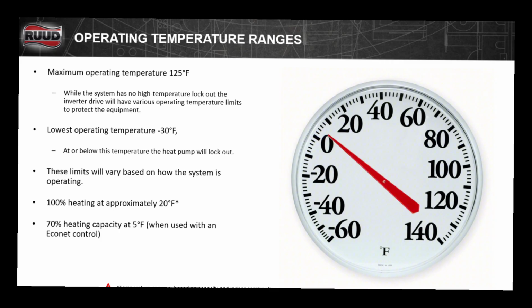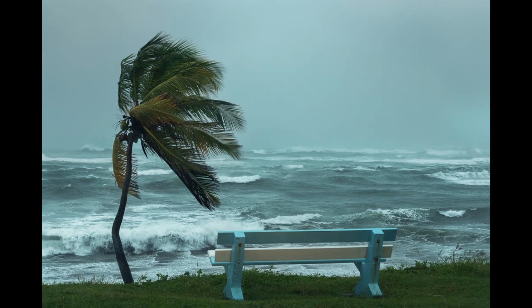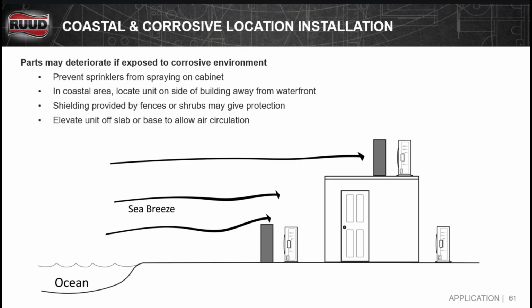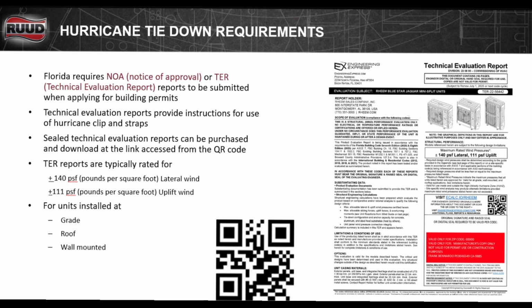The ambient temperature is also something to take into consideration. When installing the system, if the ambient temperature reaches over 125 degrees, the system will ramp down in order to save the compressor. So always keep that in mind. Because this is a side discharge condenser, we want to make sure if it's installed in a windy environment that we have some type of wind barrier in order to protect the condenser. Also note that sealed technical evaluation reports can be purchased and downloaded.